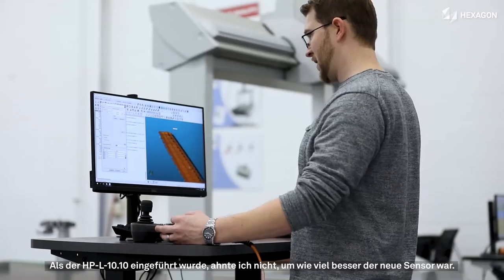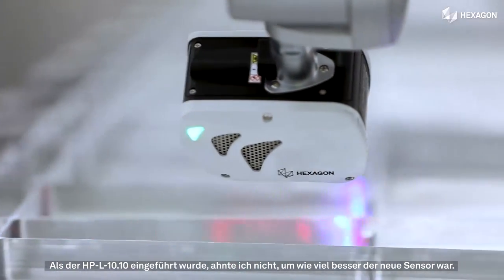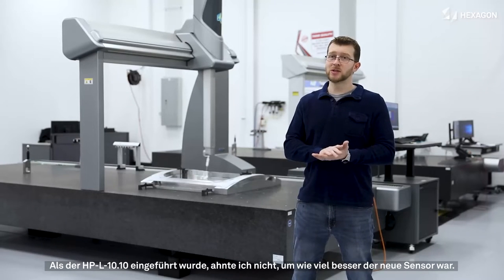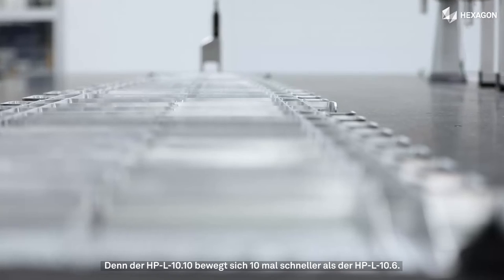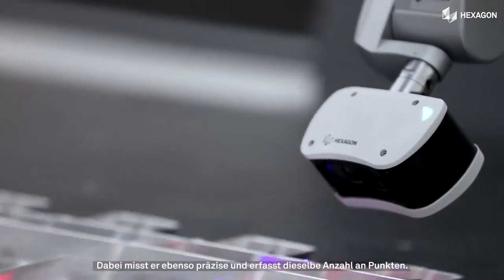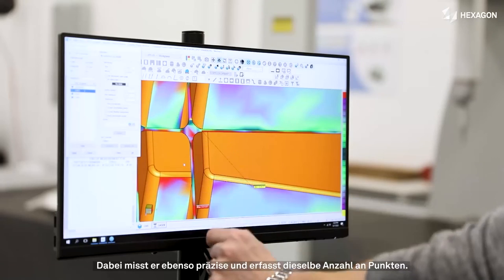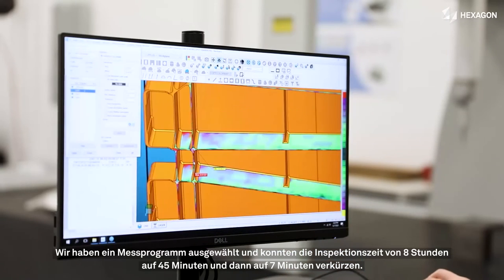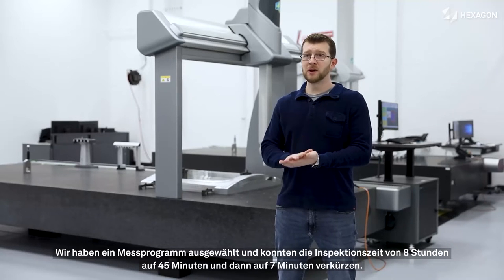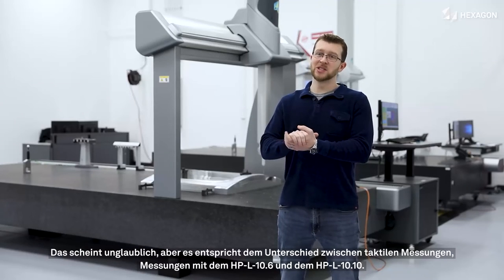When the HP-L-10.10 was announced, I didn't really understand the leap forward that was going to take place between the two sensors. But the HP-L-10.10 moves 10 times faster than the HP-L-10.6. It is just as accurate, and it actually still captures just as many points. We literally took a program, went from eight hours down to 45 minutes, and then down to a seven minute inspection time, which is just incredible.